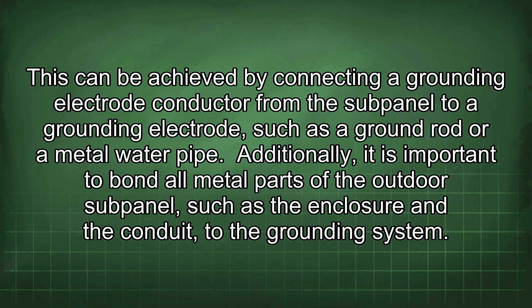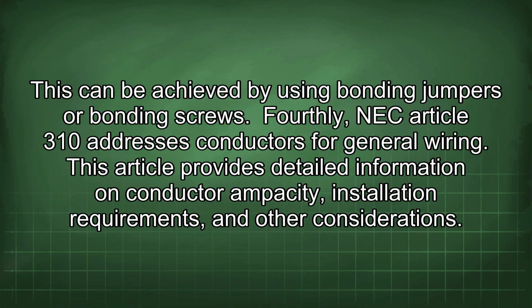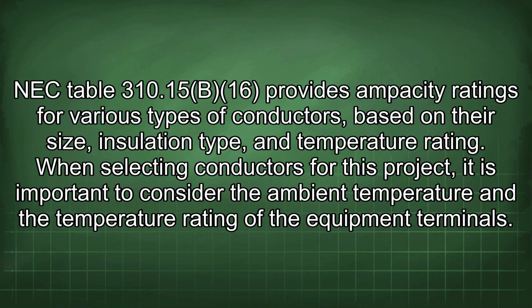Additionally, it is important to bond all metal parts of the outdoor subpanel, such as the enclosure and the conduit, to the grounding system. This can be achieved by using bonding jumpers or bonding screws. Fourthly, NEC Article 310 addresses conductors for general wiring. This article provides detailed information on conductor ampacity, installation requirements, and other considerations. NEC Table 310.15(B)(16) provides ampacity ratings for various types of conductors, based on their size, insulation type, and temperature rating.